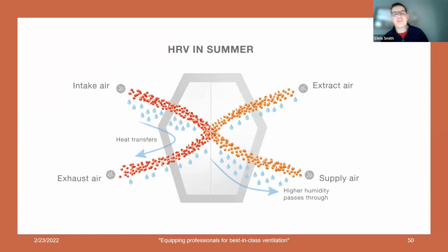Now, if we look at that HRV functioning in summer, we have a slightly different scenario. The physics of it are the same, but the results are going to change. Same thing, left-hand side of the diagram is outdoors. The right-hand side of the diagram is indoors. We have fresh outdoor air, but very hot and humid in the upper left. That's coming into the heat exchanger. We want the heat exchanger to effectively take that heat and deliver it back outside. And so it's able to do that in a heat recovery ventilator. And so the exhaust air grabs the heat and pulls it back outside. We would like to not bring in all that outdoor humidity. However, an HRV has no humidity transferability. And so the humidity from outdoors is brought inside with the fresh air.